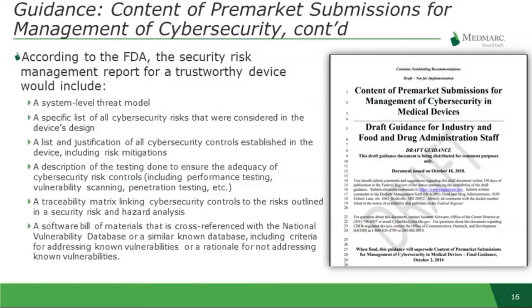Also included in the guidance document is what the FDA envisions as a good security risk management report for a trustworthy device. This would include a system-level threat model, and a list of all cybersecurity risks that were considered in the design phase. Again, this is that TPLC approach we mentioned earlier. A list of all cybersecurity controls established. Obviously, this should correspond to the risks identified. A list of testing done, a matrix linking the controls and the risks, and the software bill of materials that cross-references a national database and includes whether and how vulnerabilities were addressed, or if they weren't, why they weren't addressed.